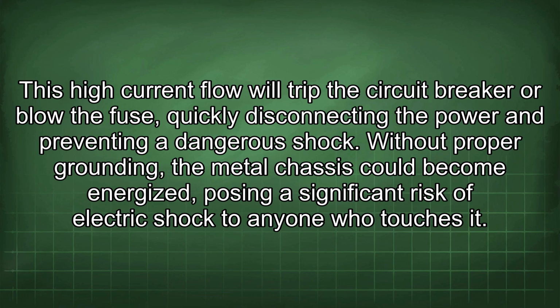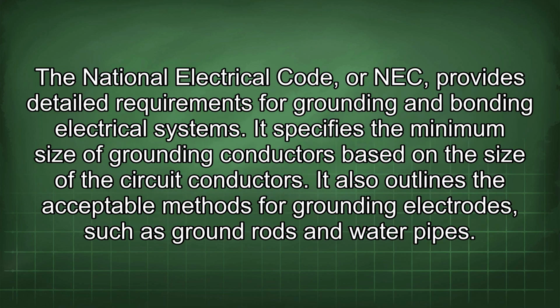The National Electrical Code, or NEC, provides detailed requirements for grounding and bonding electrical systems. It specifies the minimum size of grounding conductors based on the size of the circuit conductors. It also outlines the acceptable methods for grounding electrodes, such as ground rods and water pipes.